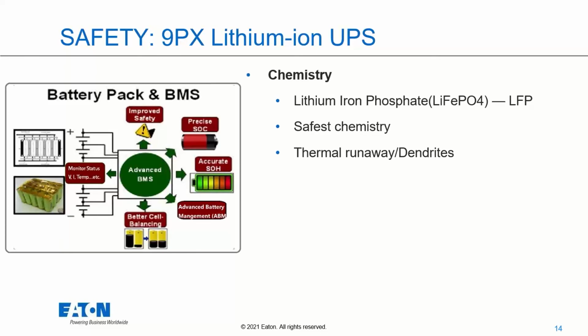For chemistry selection, LFP, or lithium iron phosphate, was chosen due to it being one of the safest lithium ion chemistries widely available, due to its high thermal runaway temperature and tolerance to voltage variation. As part of DOT UN 38.3 testing, the case temperature of cells may not exceed 170 degrees Celsius or 338 degrees Fahrenheit. Since the LFP cells used in the lithium ion UPS have a thermal runaway point much greater than this temperature, the risk of thermal runaway when exposed to situations like the test conditions is further reduced.